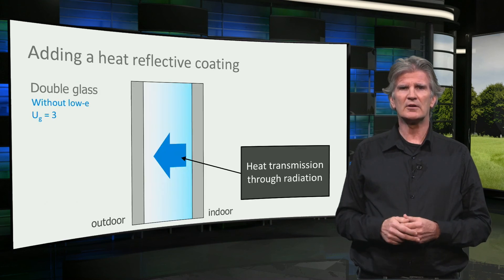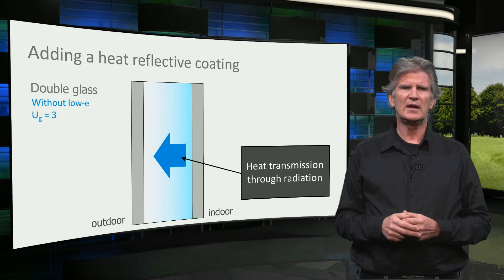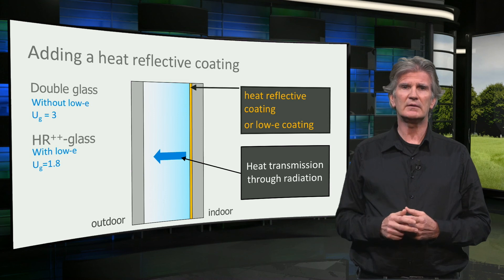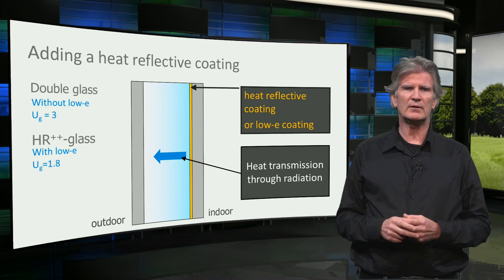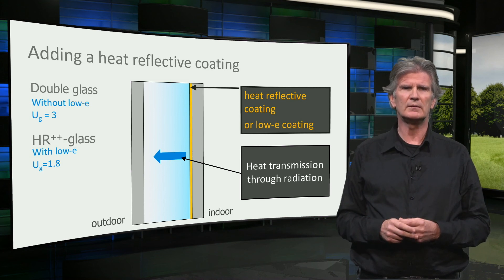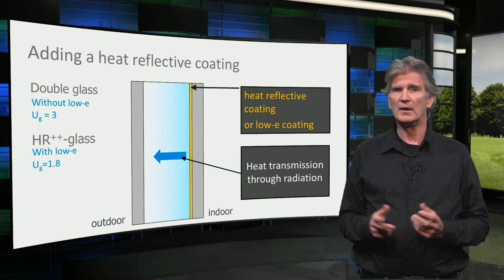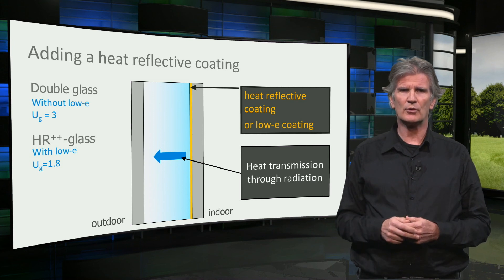The second technology is to apply a so-called low-E coating, which reflects the infrared radiation and reduces the heat transmission through the cavity. This coating is a very thin, invisible layer of just a few molecules of metal. By adding this coating, the U-value of double glazing can be reduced from 3 to 1.8. Glass with this type of coating is called HR++ glass.